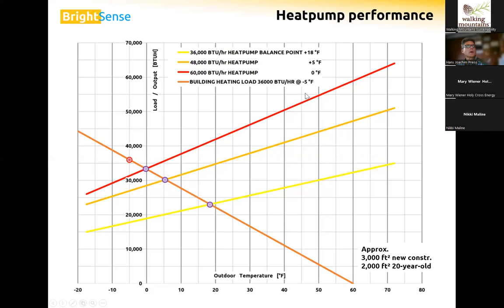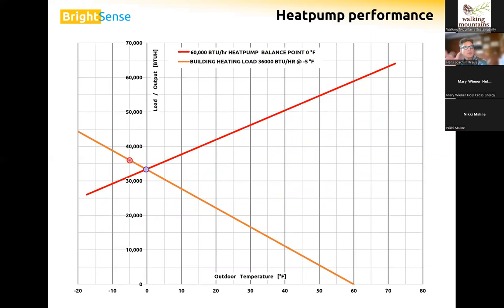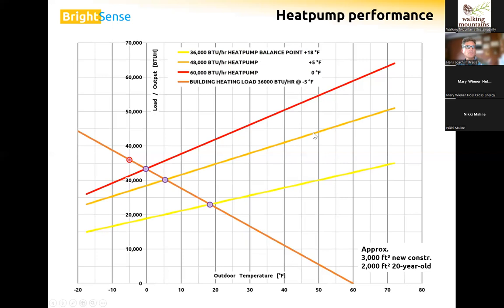The reason why these are lower than the 60 is supposed to be at 60,000 at 47 degrees, but we are quite a bit lower than that. We are at 53,000 here, and that's again because of our altitude derating. The heat pump absorbs thermal energy from the thinner air outside, so that's why we are not getting quite the full output here at altitude. The nominal output is measured at sea level.